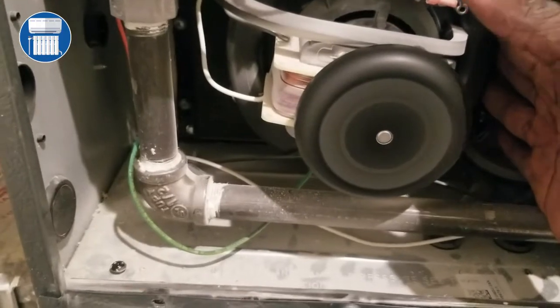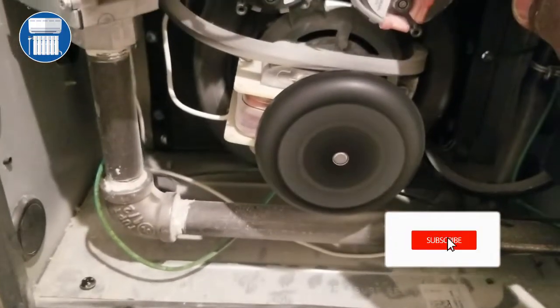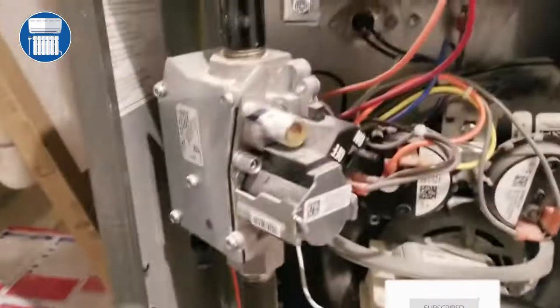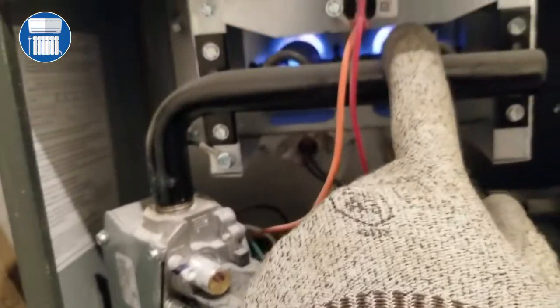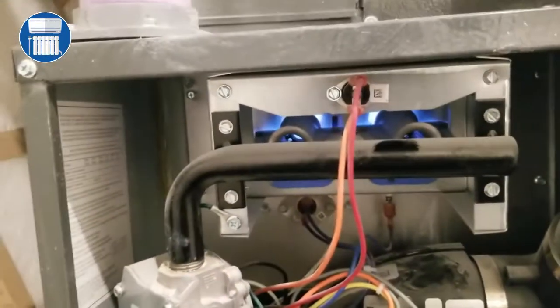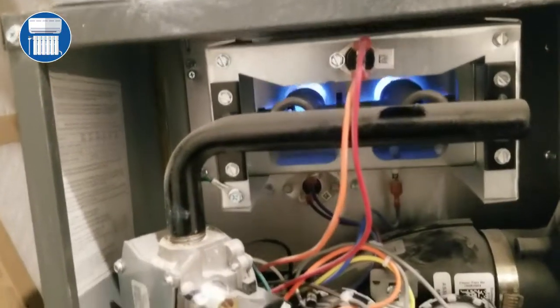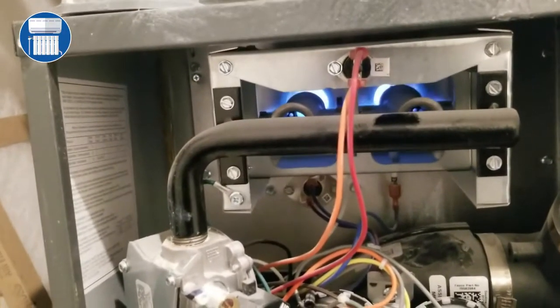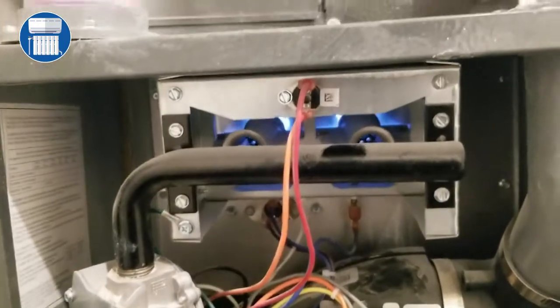So right here we are at the top of the furnace. This is your induced motor here. See it spinning. This is your pressure switch here, your gas valve here, and these are the major components, and these are your rollouts. Most times, look for those rollouts. They would trip sometimes. If your vent is closed upstairs, you can actually show a code. So that is one of the issues.